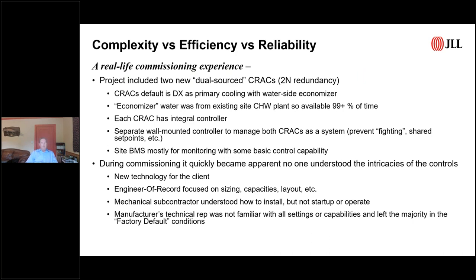So, my real life experience: I was on a project, a very small data center, more of a server room. It only had two CRAC units in it. They were dual source, so each CRAC unit had the combination of a fan coil as well as a DX unit built into it. DX was primary, and the water coil was considered an economizer coil.